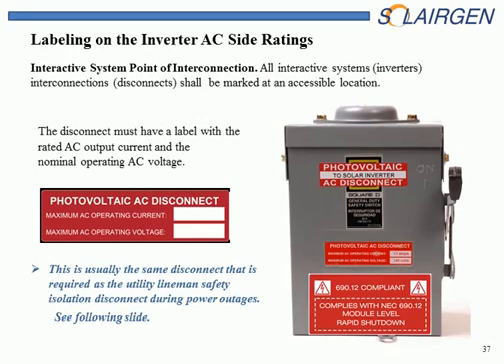The NEC also requires that an AC disconnect, labeled and placed in a readily accessible location, be on site. Now, it does state that if it's not outside by the meter, there has to be a plaque out there. But the utility is also stepping in on this one. They require that there's an AC disconnect that's labeled as well, so usually this is one and the same. So if you don't see it next to the meter, there should be a plaque right next to it describing where it's located. And the utility company doesn't allow this to be inside of these structures, so you should see one of these AC disconnects outside of a structure on all installations. Commercial, they're allowed to have it in a locked electrical room, so that's an exception.